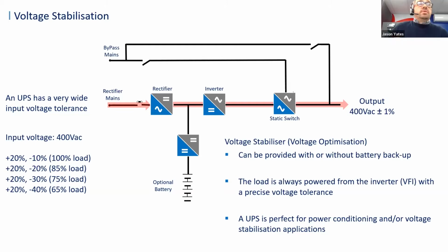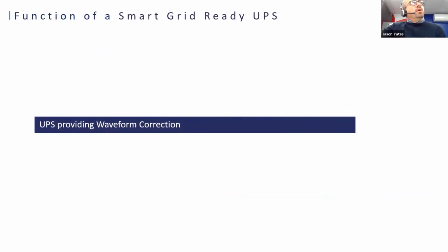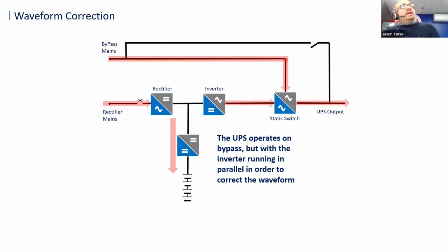So that is another good thing, that again this can be dynamically controlled. Another thing that a smart GridReady UPS has is a function called waveform correction. Again, this is the typical diagram of an online dual conversion UPS. In this case, however, we now have two power flows. We have the power flowing into the UPS system via the rectifier, and we also have the mains power that is passing through the bypass line.